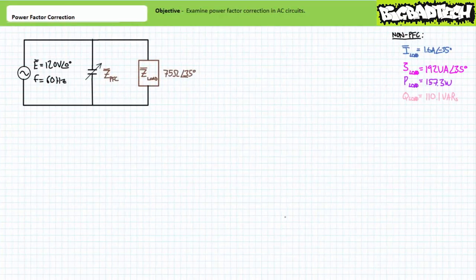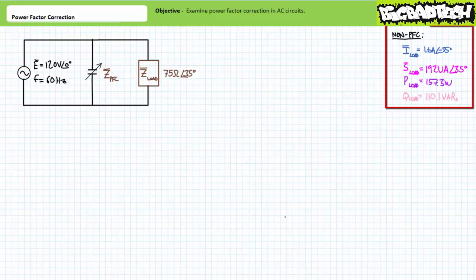Let's return to our previous illustrated example and see if we can power factor correct it, and then compare and contrast the electrical properties with our previous implementation. As our previous calculations demonstrated, our electrical load exhibits inductive characteristics, and we need to install a variable power factor correcting capacitor in parallel. Then, we need to adjust this capacitance value such that it power factor corrects the system.